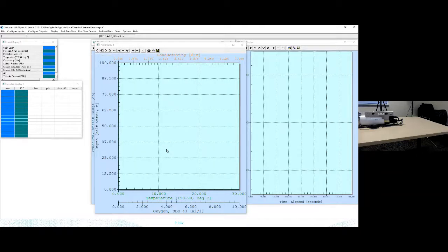And then I'm going to open up this serial ports tab. This is where I can specify the COM port that I want to use to communicate with my CTD, baud rates, data bits and parity, etc. And if you're using additional things like a water sampler, serial data outputs, and a remote display from your deck unit, this is where you'd specify that as well. But we're not going to do that now. We just care about the CTD serial ports. Okay, so now Seasave is presumably able to connect to our CTD.